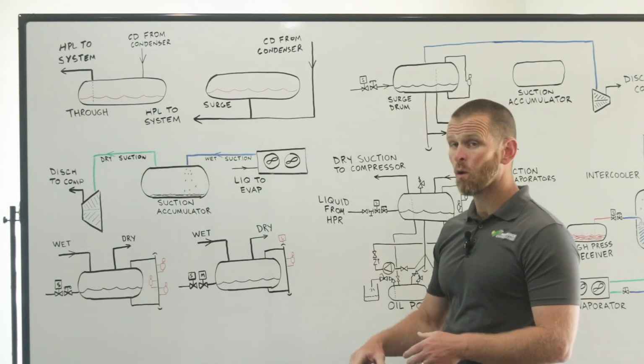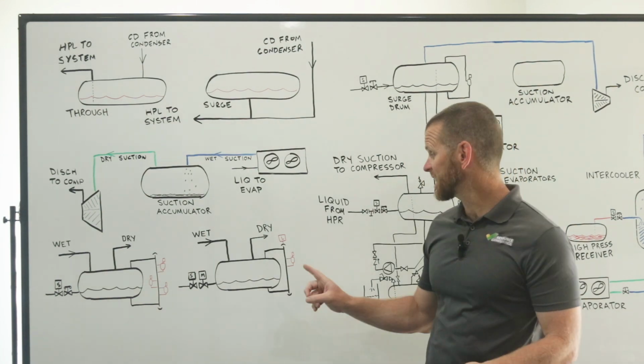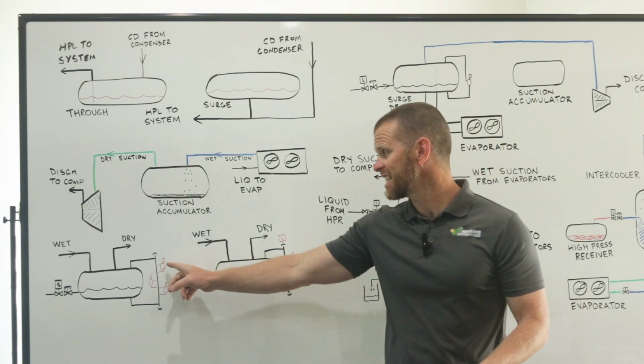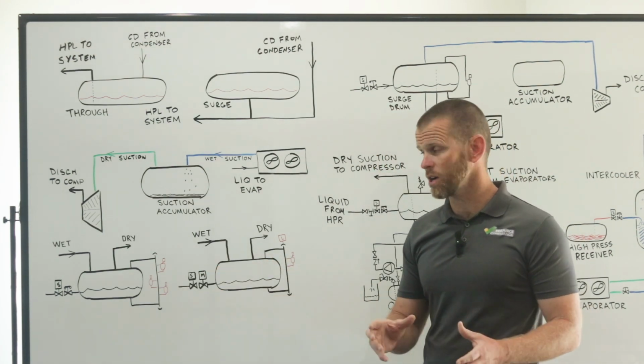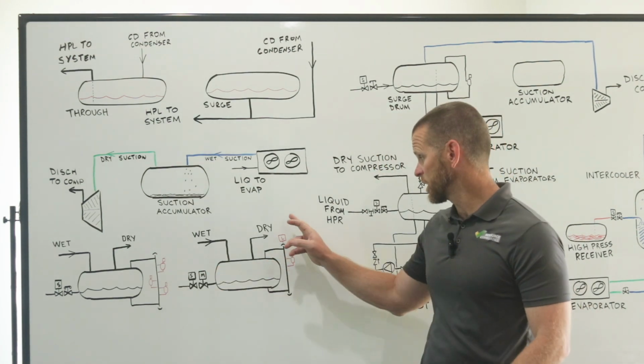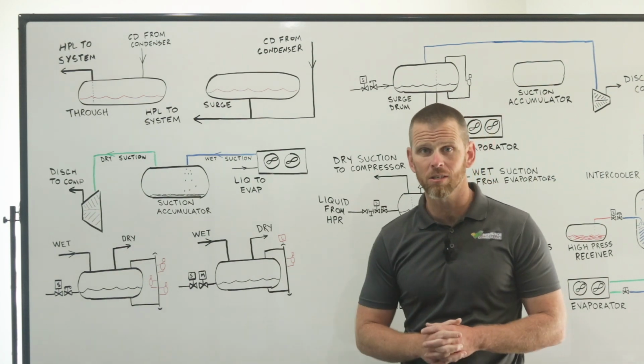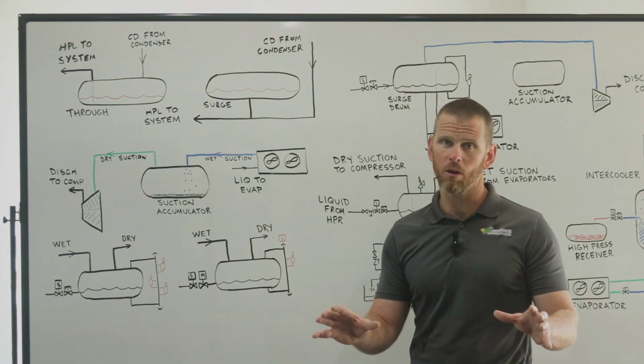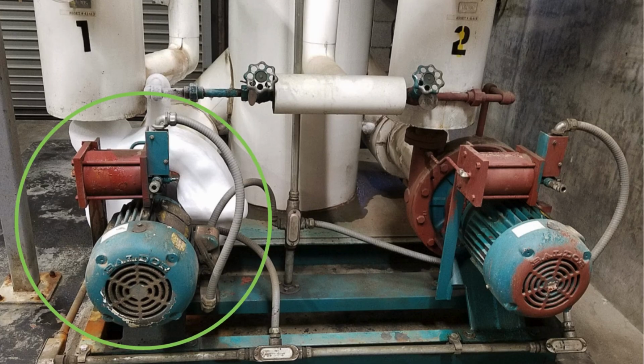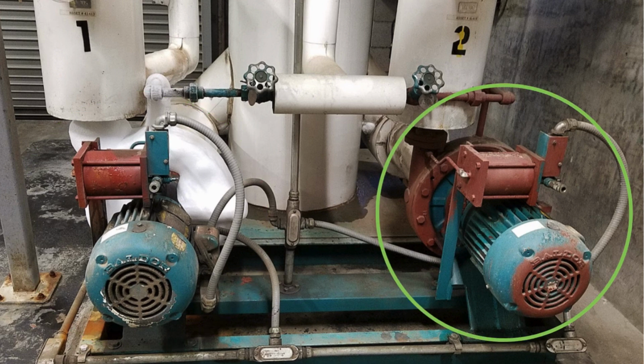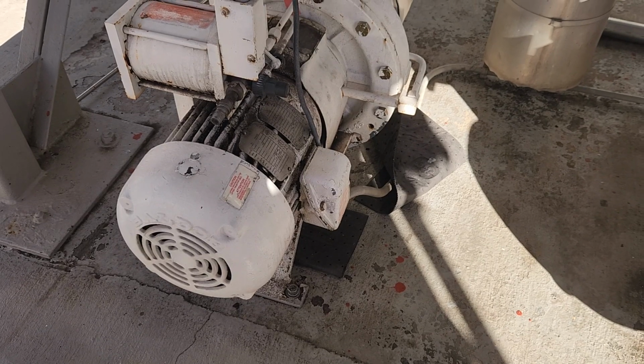So what's the float switch for? Well, really that becomes a backup at this point. It's still a high level float switch, exact same function as we had on the float tree. And we do that simply as a backup. If this probe fails, we still want to protect those compressors, make sure they don't get slugged with liquid. Most often, a recirculator will be equipped with 2 pumps to provide redundancy if one pump fails.